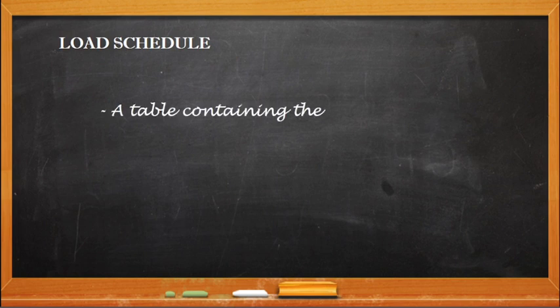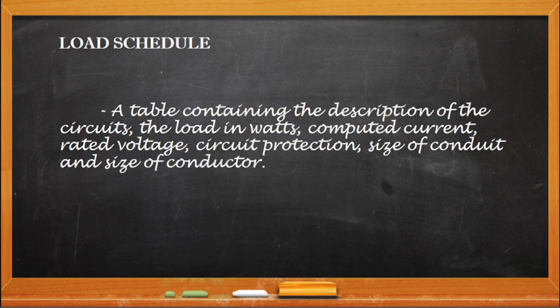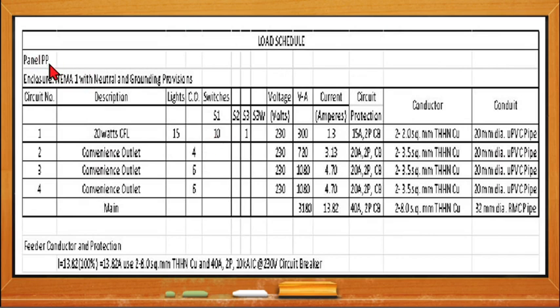Then we have the load schedule. The load schedule is a table containing the description of the circuits and the load in watts, computed current, rated voltage, circuit protection, size of conduit, and size of conductor. For example, in panel PP (power panel) with NEMA 1 enclosure with neutral and grounding provisions: circuit 1 has 20-watt CFL lights, 15 pieces, with 10 single pole switches and 1 three-gang, at 230 volts, 300 volt-ampere, 300 watts, 1.3 amperes current, 15-ampere circuit protection, 2.0 square mm two-wire conductor, and 20 mm diameter UPVC pipe conduit.